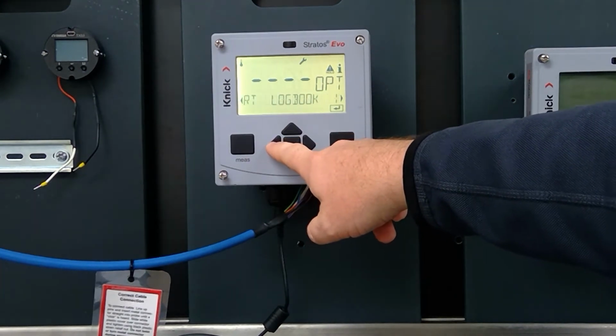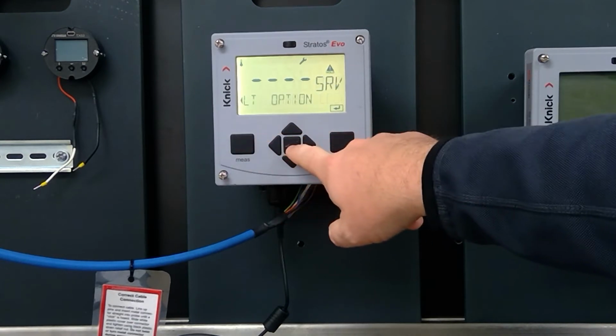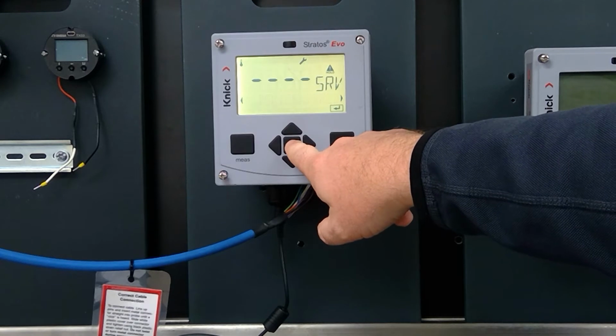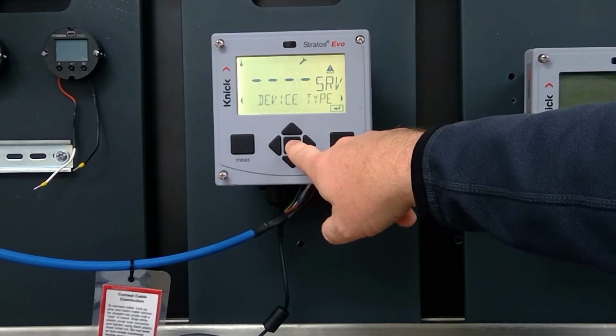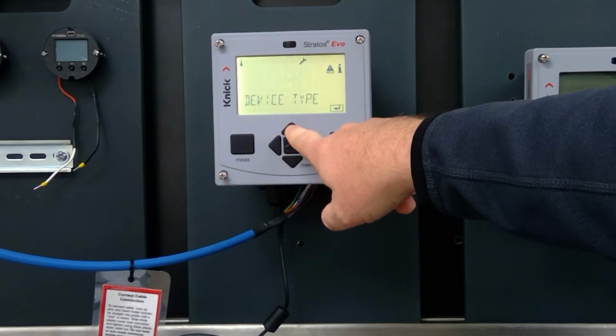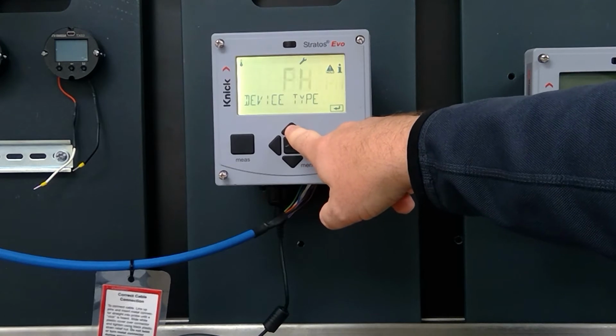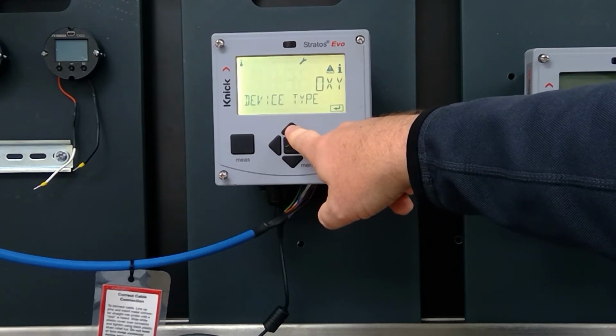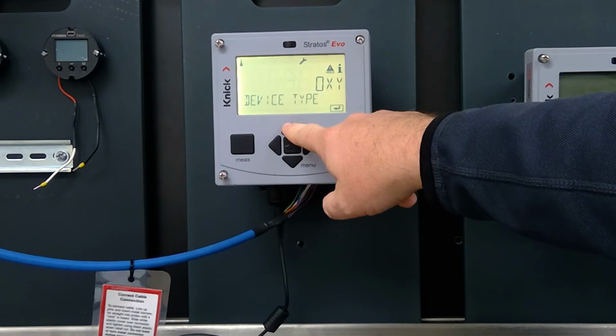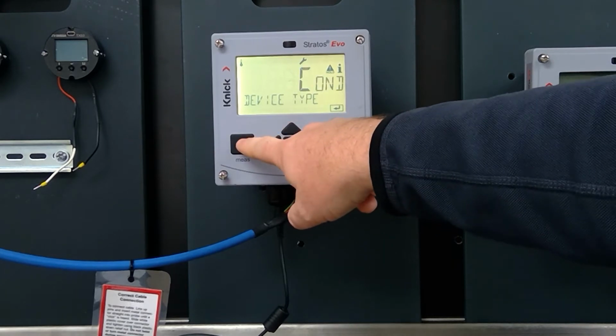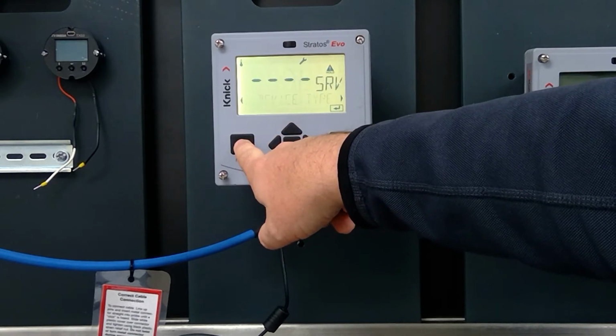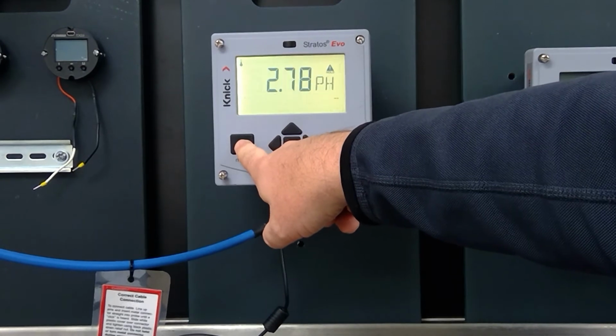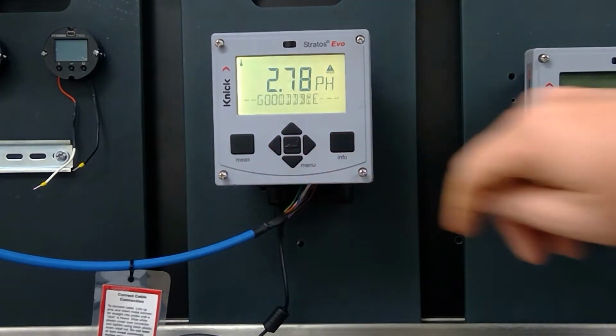The other thing we want to make sure is that we have the correct device type, and in this case, this transmitter is already set up for pH, but if it wasn't, you could go through and select the correct device type that you need. In this case, you won't see pH pop up because it's already in pH mode. So I'll just hit measure 3 times to go back to the measurement screen.